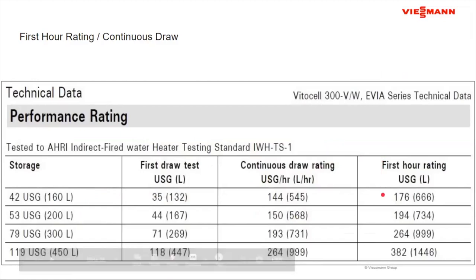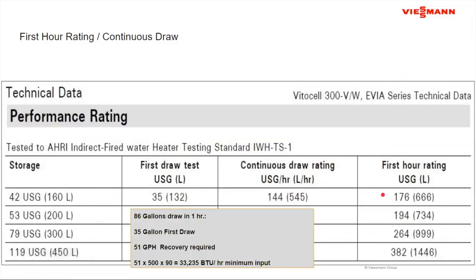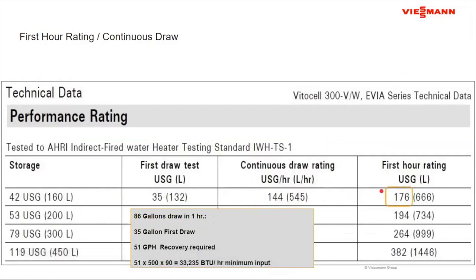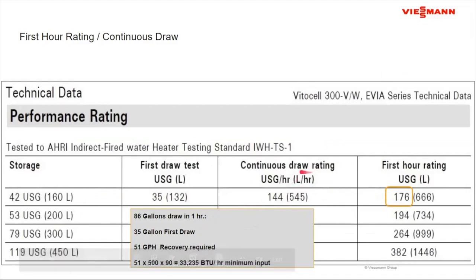The lowest one I have is 176 gallons. Yeah. So if I need a maximum of 86, 176 is certainly more than that. That becomes my choice, okay? Now, when I look at this, a couple of things come into play. These numbers are based on a certain package that AHRI puts together with the manufacturer to test the tank. It's not the same package that's going into the basement of this house.